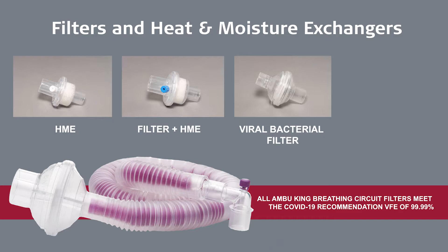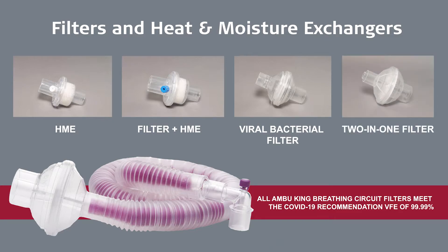Note that HME devices, whether they're combined with a filter or not, have to be placed close to the patient's airway to be effective, because if they're not close to the patient's airway, they can't maintain moisture in the patient's airway. Filters, on the other hand, are effective at the patient end or the machine end. So if you're using a combination device, it has to be at the patient end.